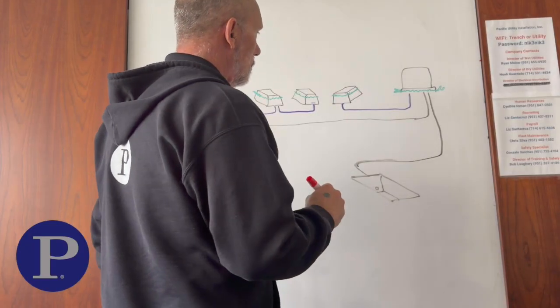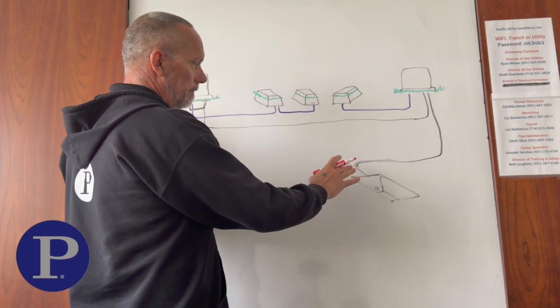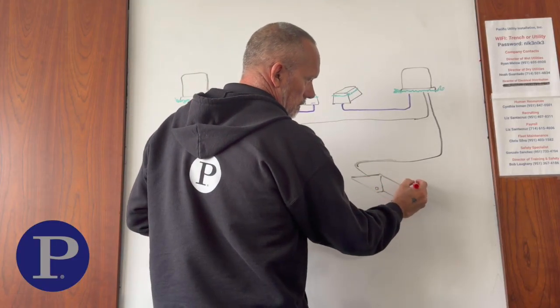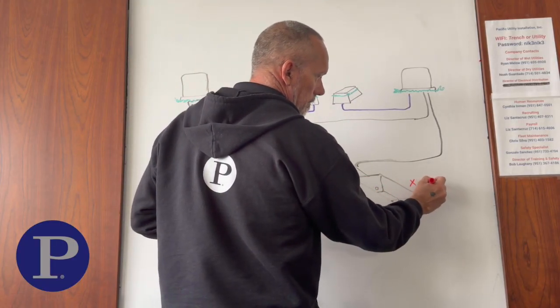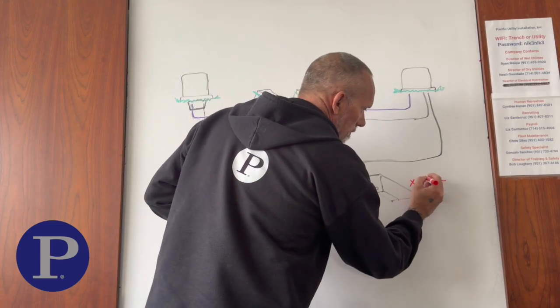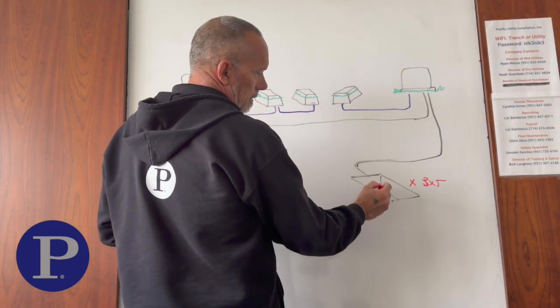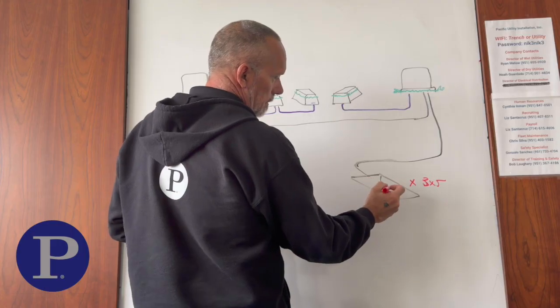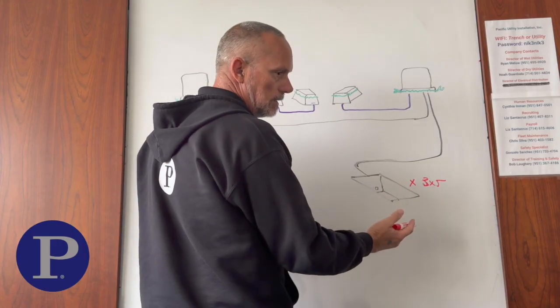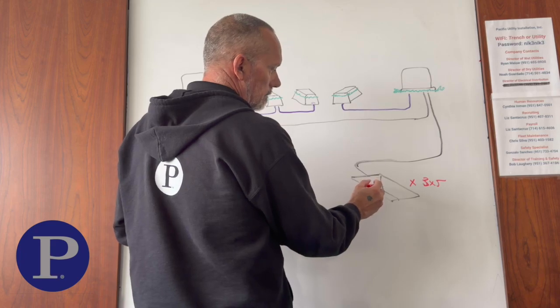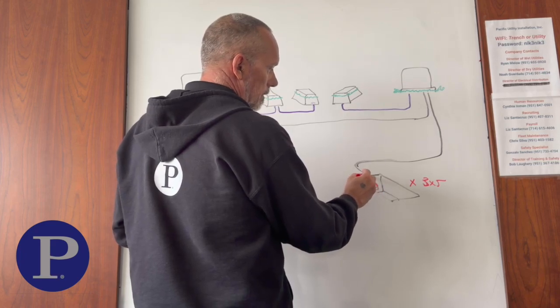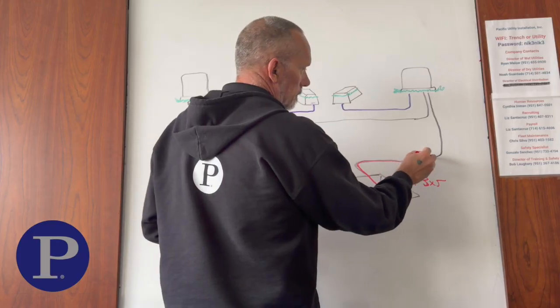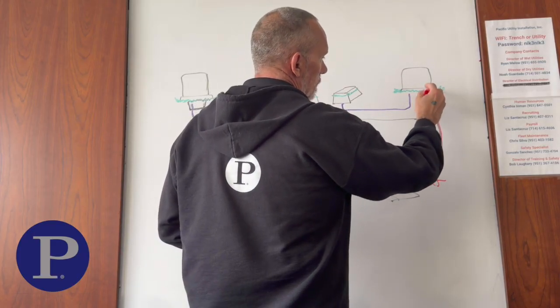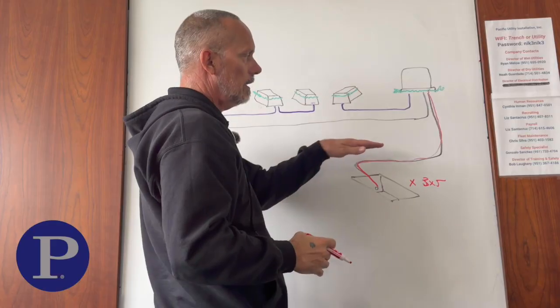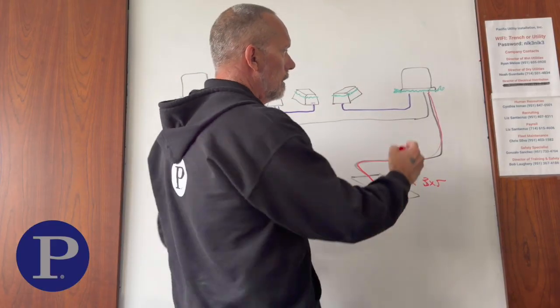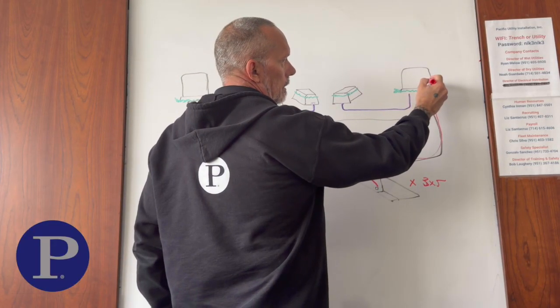Okay, so this is a basic diagram. What I've drawn here is, I'm going to call this a pull box, maybe a 3x5 pull box. This is going to be, we'll call this a source. It's existing, it's already energized. What we're going to do is pull from this primary source. It's going to come over here and feed up into the transformer.